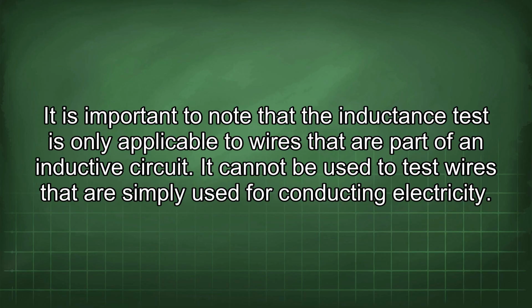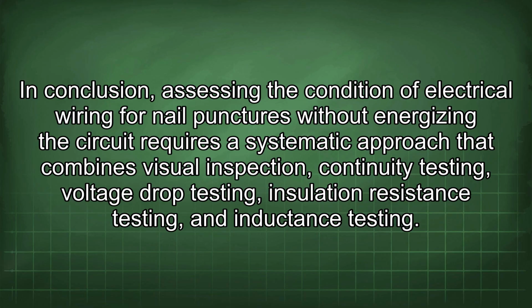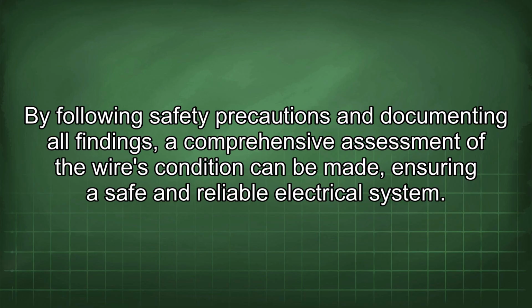It is important to note that the inductance test is only applicable to wires that are part of an inductive circuit. It cannot be used to test wires that are simply used for conducting electricity. In conclusion, assessing the condition of electrical wiring for nail punctures without energizing the circuit requires a systematic approach that combines visual inspection, continuity testing, voltage drop testing, insulation resistance testing, and inductance testing. By following safety precautions and documenting all findings, a comprehensive assessment of the wire's condition can be made, ensuring a safe and reliable electrical system.